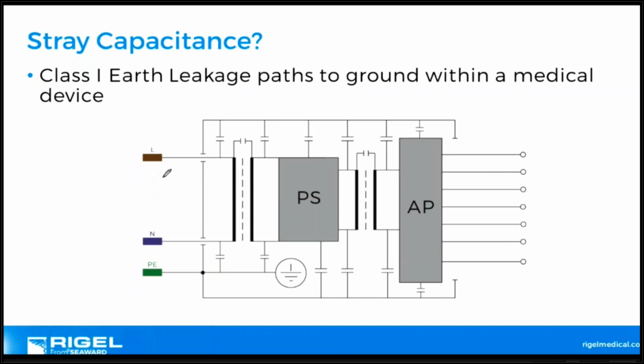So if I've got my functional current, it would flow between live and neutral, between hot and neutral. And let's say I've got 100 milliamps flowing in this direction, but I've only got 99 here. Well, basically the leakage current is 100 minus 99, and that would be equal to 1. So we've got 1 milliamp escaping the system. How does this escape? You've got conductors within your system, these are conductors that carry current. This would be some kind of isolation barrier. This is our power supply. This is another isolation barrier, and this is our applied part.